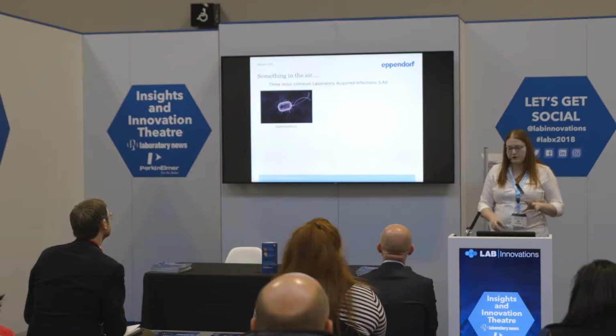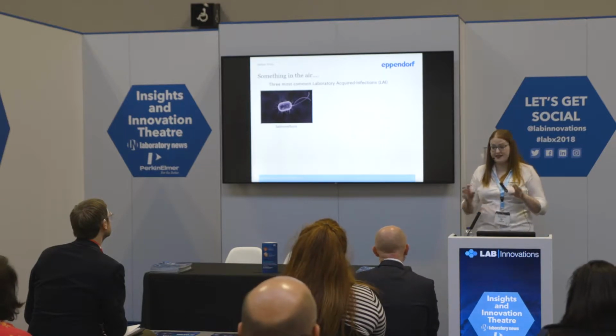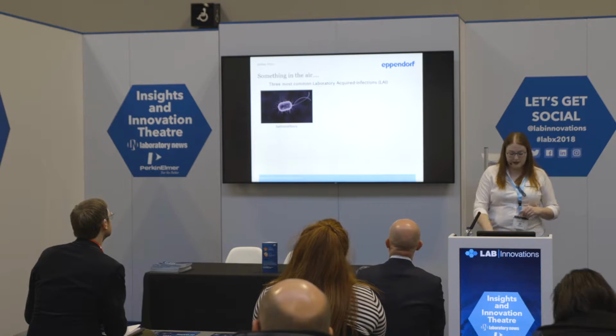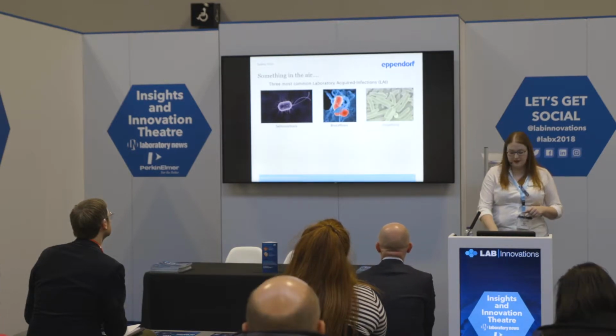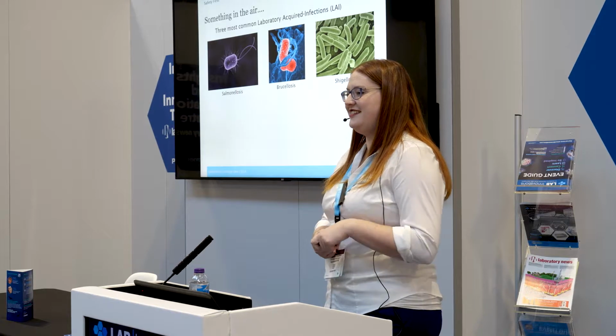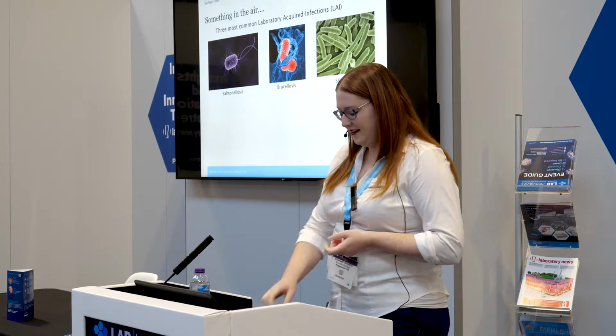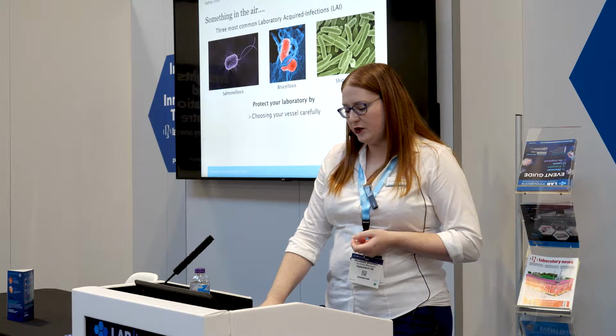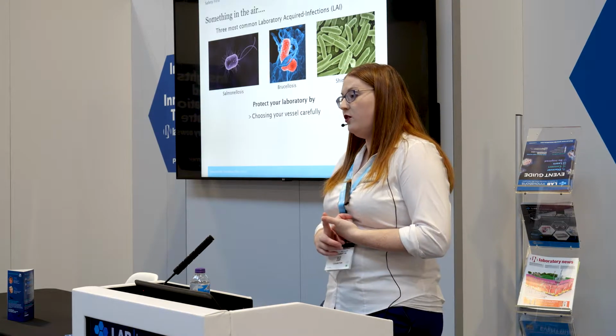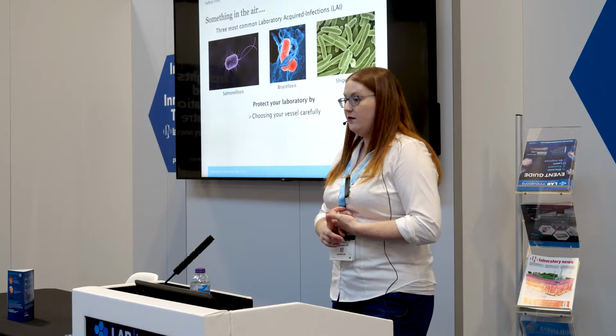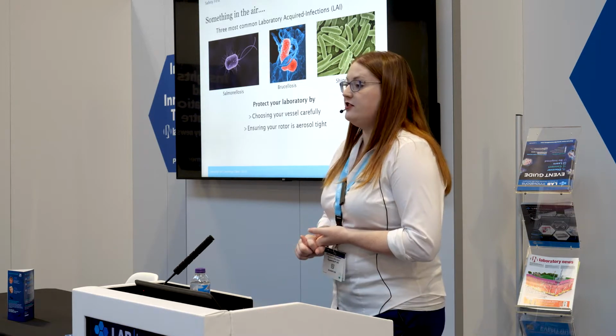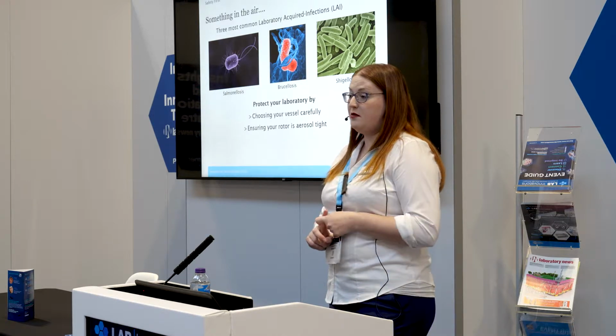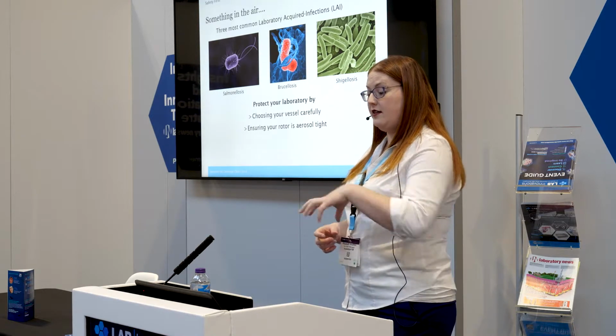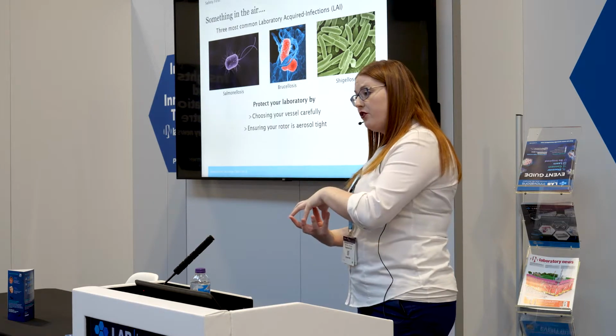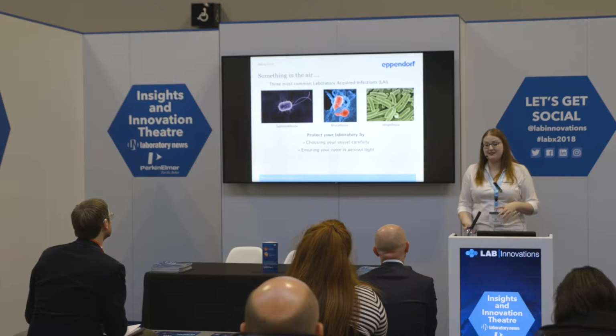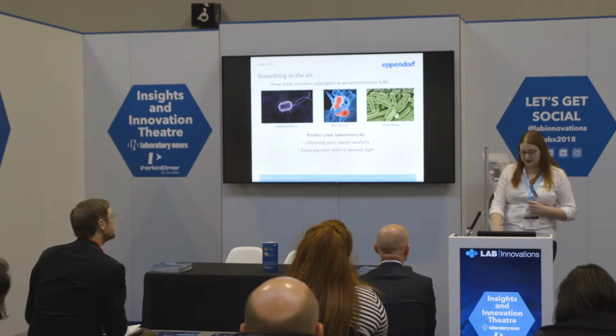The three most common lab infections that people get as contaminations from their samples are salmonellosis, brucellosis, and shigellosis. None of these are nice infections. You do not want them. So it's really important to protect your lab by thinking about what you're using your sample in, by ensuring your centrifuge rotors are aerosol tight. On Eppendorf ones, they will say so, but they will also have either a red knob in the middle or there will be caps. It is something to think about, and your rep should be asking you if you're purchasing whether or not you need aerosol tight.